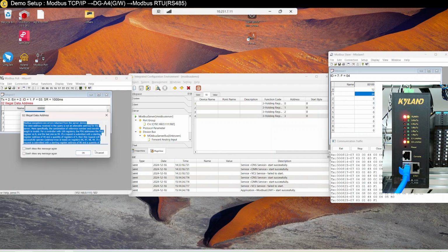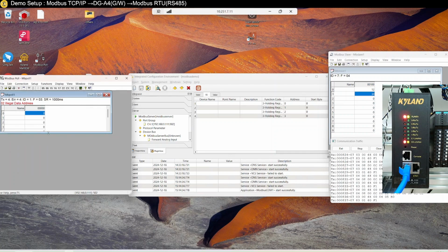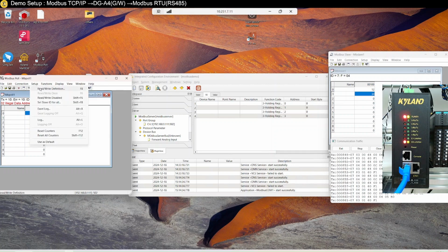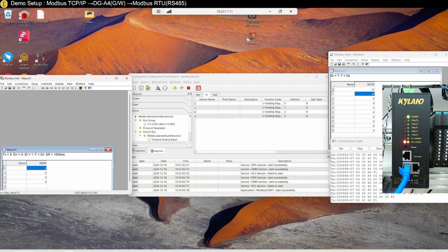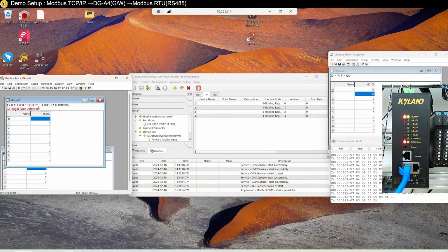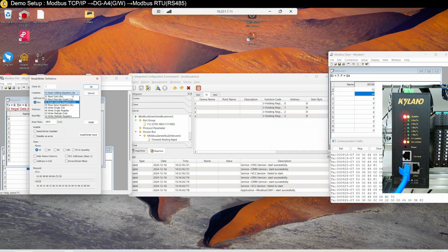Yeah, quite straightforward. Okay, we got illegal address because I'm reading a length of 10. I'm supposed to read at a length of 4. So if I put 4, it shouldn't have any error. Now I'm good. So this is the function code 3, which is the holding register. Let me create another one and change this to function code 4, for reading the input register.